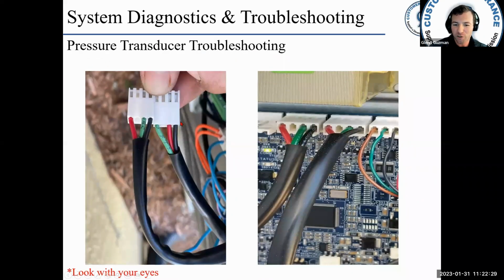Same thing, going back to this one, check your transducers, make sure the transducers are wired properly. The unit is very good at keeping itself in check, but if it's receiving the wrong information, then it's going to act according to what it's receiving. It's like when I'm helping a guy troubleshoot a system and I say, okay, check your voltage here, check your voltage there. And we're going down the circuit in a proper troubleshooting format. And he says, well, I have no voltage here. I'm like, but you just told me you had voltage there. It's impossible. You're giving me wrong information. So I'm going to misguide you if you give me the wrong information. Well, the system acts the same way. If it has the wrong information, it's going to act accordingly based on that information. So we've got to look at that when we're troubleshooting these units.